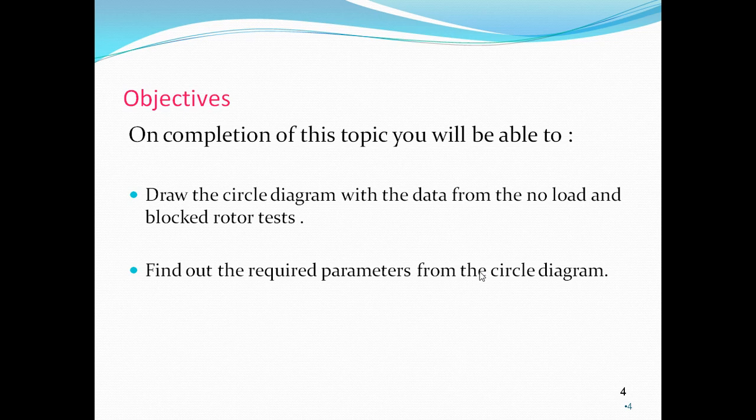For conducting the no load test, we keep the rotor at no load, that is at open circuit, and we apply the rated voltage. Then we take the readings of voltmeter, ammeter, and wattmeter.